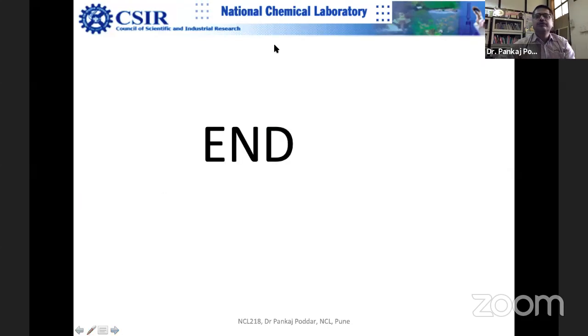I hope that I did this big exercise to give you this message: why thinner the better is important, and why you should worry about chromatic aberration, astigmatism, apertures, cleaning and maintaining all of that. You should not introduce any wet sample into the chamber.